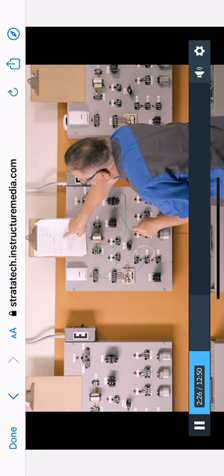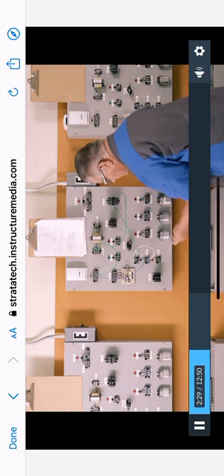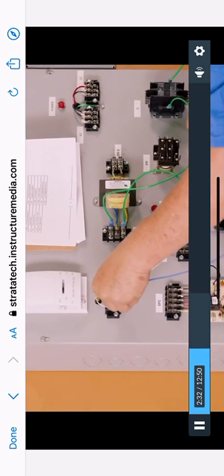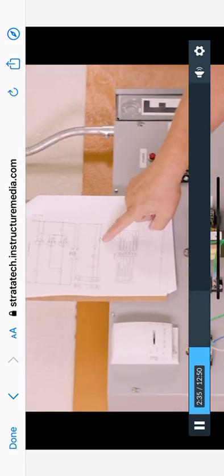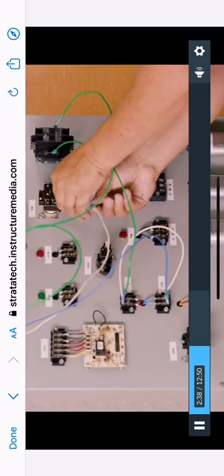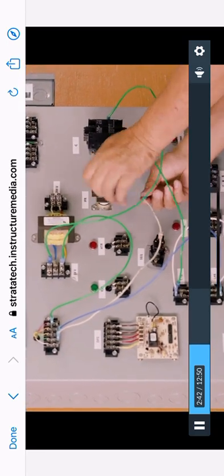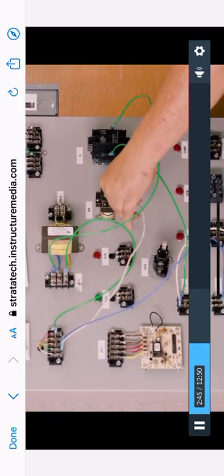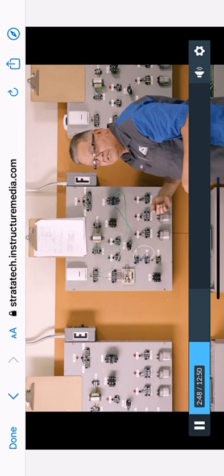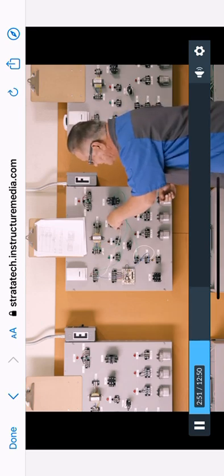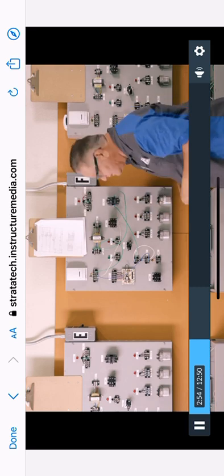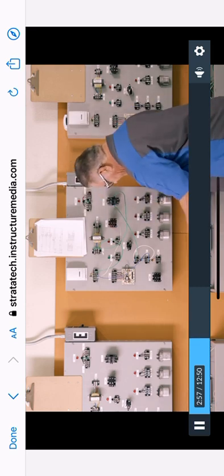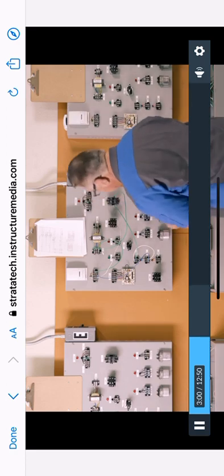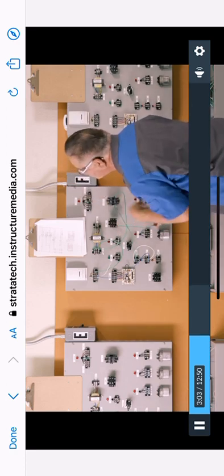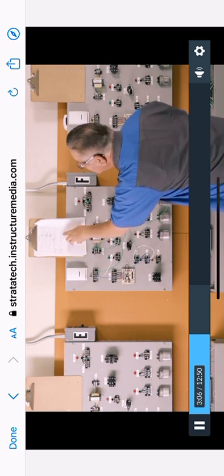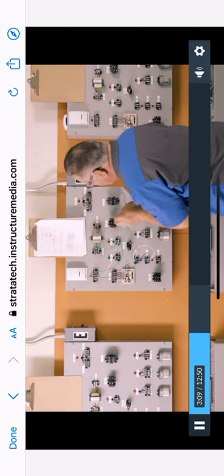Now we got the G circuit, which is your fan. So I go from my G wire, which is the green, I go straight to my indoor fan relay, which is the coil. Coils are always on the bottom, switches are always on the top. So I go to my coil, one side. It doesn't matter which side you go on your coil. Okay? I can go on this side or I can go in on this side. It doesn't matter what goes in, what comes out on the coil. So I'm going to go in on one side. I come out on the other side of my coil. So I just ran this wire to my indoor fan relay coil. Now I'm going to come out and I'm going to go straight to my common.